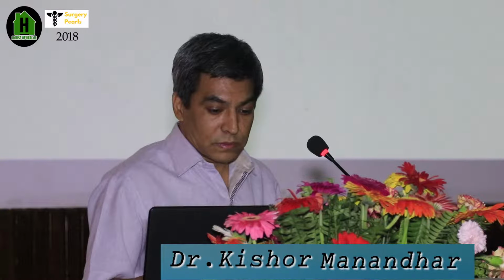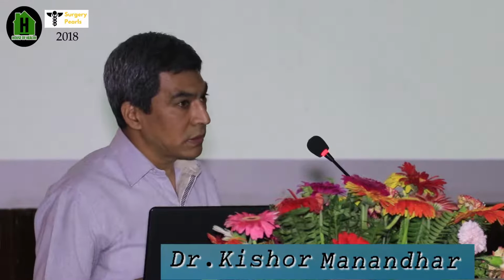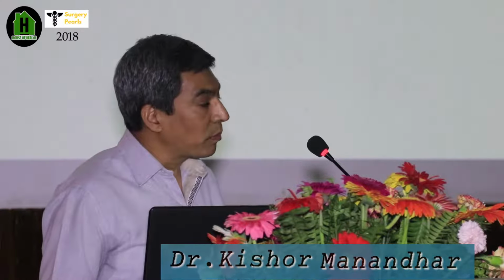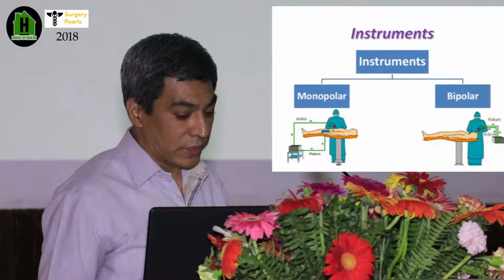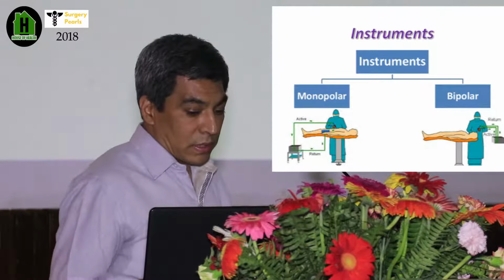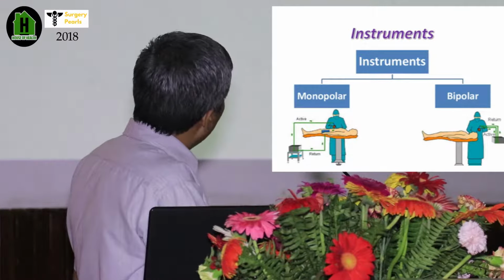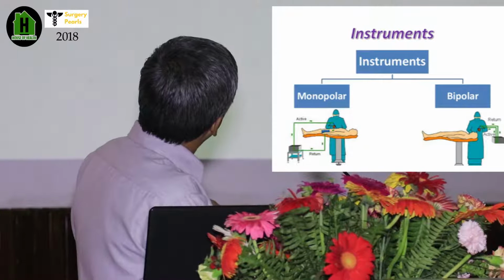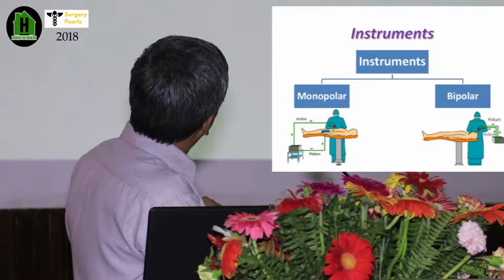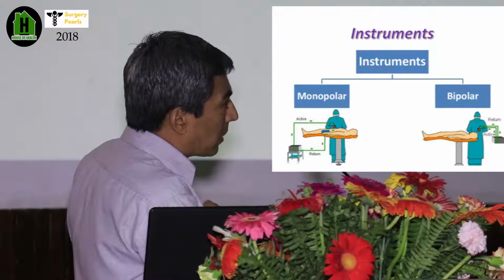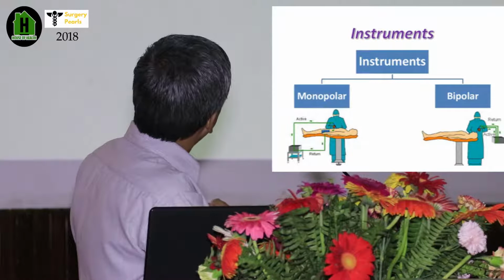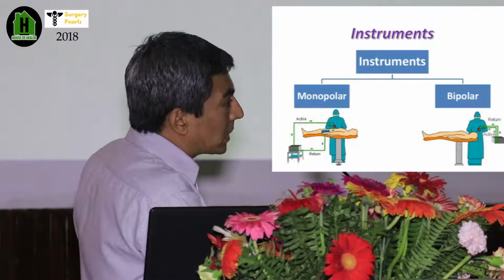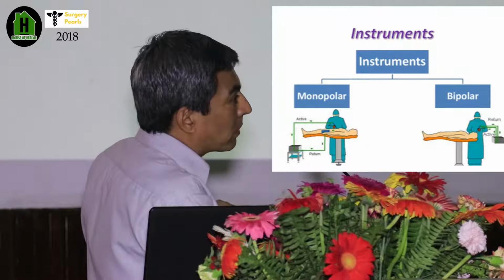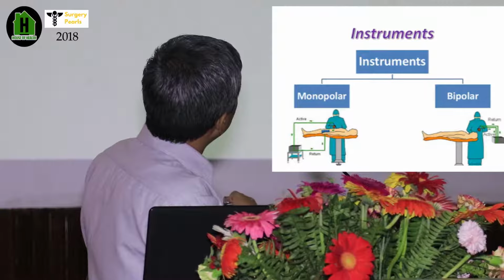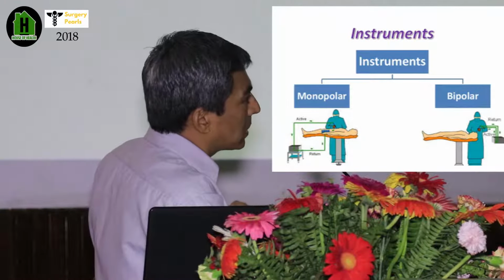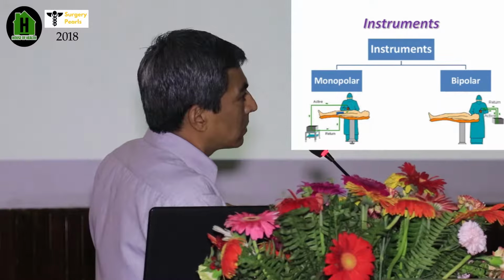So there are two different modes in these electrosurgical units. One is the monopolar and one is the bipolar, as you all know. But here, the difference between the mono and the bi is, in the monopolar, there is a passive electrode with a high surface area, and the circuit is completed through the patient, the whole body of the patient, or the tissue in between the active and the passive electrodes. Whatever is the tissue in between these two electrodes.